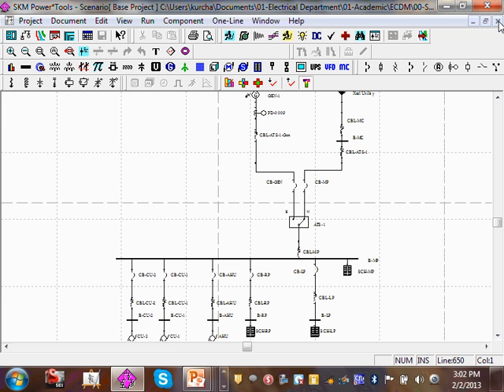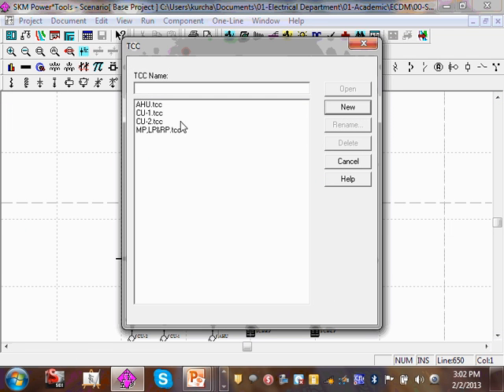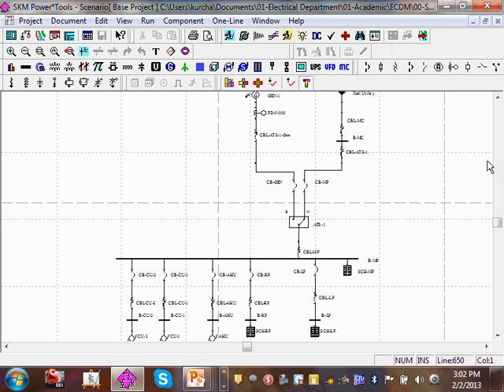The exciting stuff is going here. Now, before I take you guys there, here's my available fault. Here's the coordination. I have my circuit breakers here, and I have a bunch of circuit breakers here. If I have a short circuit right into this air handling unit, which circuit breaker do you want to trip? The one in front of it. What is that called? Overcurrent protection coordination, selectivity. It is required on hospitals, for example. Emergency systems require it. Okay, so how do you do that? And that's part of our presentation today.